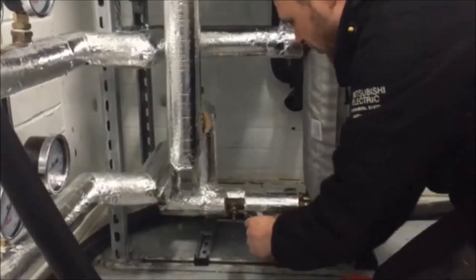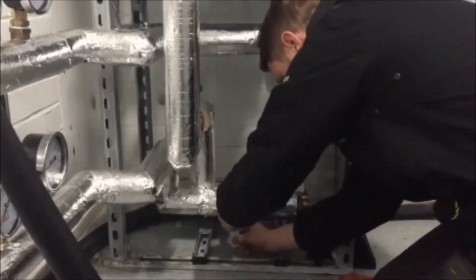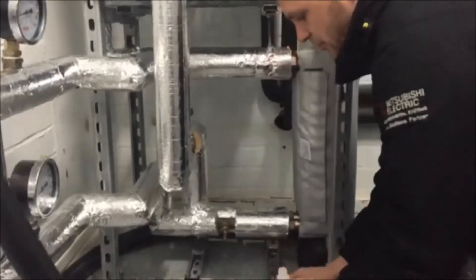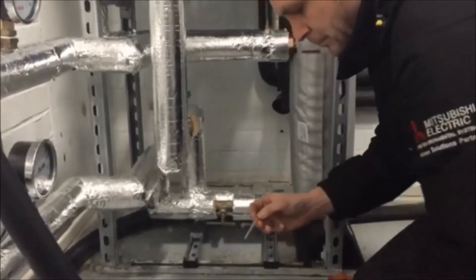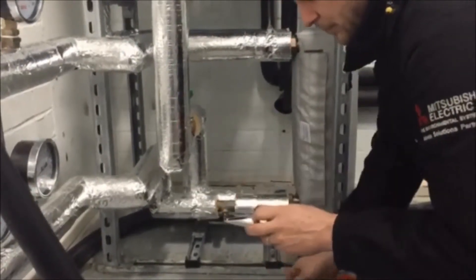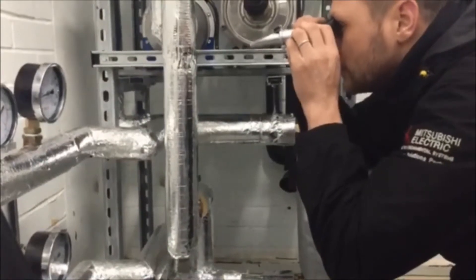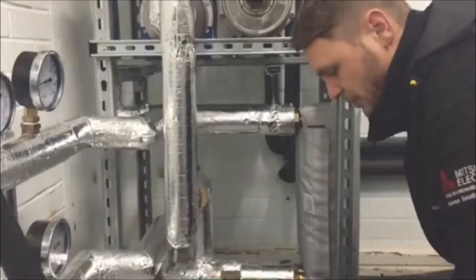I've been taking a glycol sample from this chiller unit, and I'm going to measure it using a refractometer. The reading is minus 5, but I'm trying to achieve minus 10, so I need to put some more in.